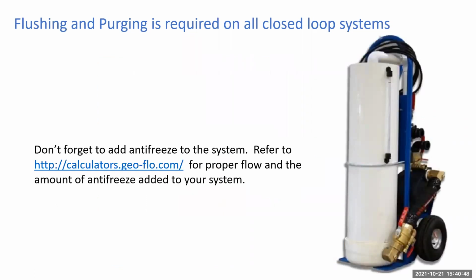So flushing and purging is required on all closed loop systems. And you want to do this with three-way valves, as needed, at your pump motors or flow center. And you want to do this with a minimum flushing velocity of 2 feet per second. So basically, the bigger the motor you have, the faster you can push the water. And you want to get the micro bubbles out of there. Those micro bubbles will eventually become one bubble or several larger bubbles, and they will cause more issues. You want to put an antifreeze in there. Most anybody anymore uses glycol, propylene glycol. It's just the food grade, inside city limits and everything, they want you to use that. Used methanol and ethanol before.